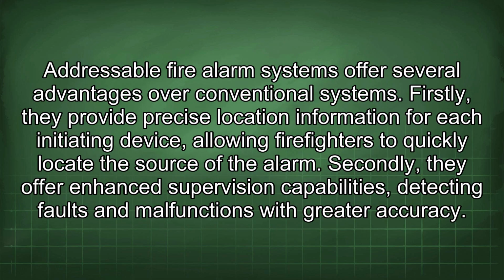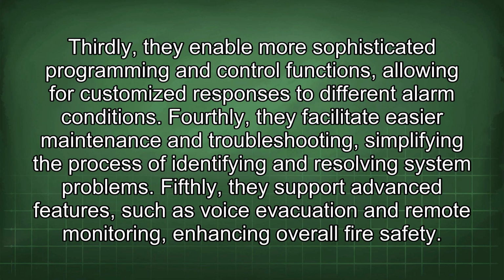Addressable fire alarm systems offer several advantages over conventional systems. Firstly, they provide precise location information for each initiating device, allowing firefighters to quickly locate the source of the alarm. Secondly, they offer enhanced supervision capabilities, detecting faults and malfunctions with greater accuracy. Thirdly, they enable more sophisticated programming and control functions, allowing for customized responses to different alarm conditions. Fourthly, they facilitate easier maintenance and troubleshooting, simplifying the process of identifying and resolving system problems. Fifthly, they support advanced features such as voice evacuation and remote monitoring, enhancing overall fire safety.